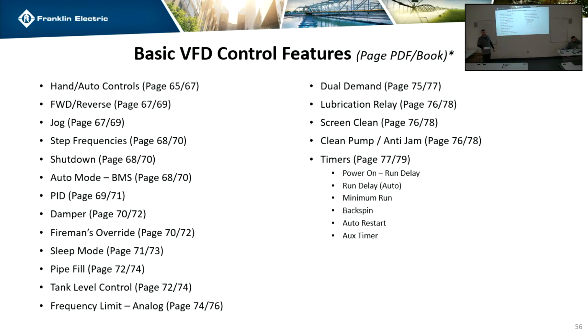So say you're clearing out a stairwell in a fire situation, you could have it running off the PID to not overpressurize it, yet still pull out the smoke. Correct. You still get the doors, and then if say the drive fails for whatever reason, can you set it to automatically change over to bypass? No, it's one or the other.